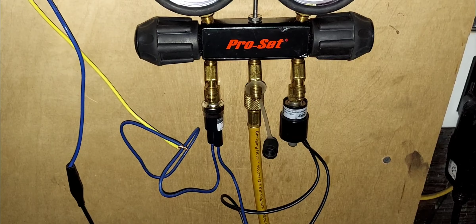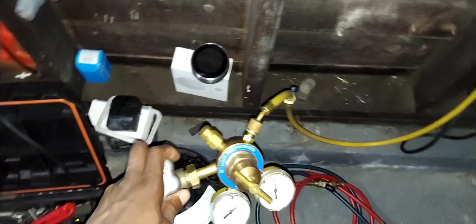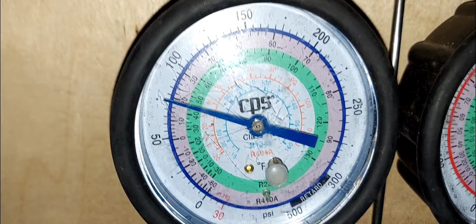So we're going to go ahead and trip this switch. We're going to trigger it. We know we've got to go up to 410 psi, so let's just close this gauge right here. So we're done with the low side. As a matter of fact, I've got to build the low side up and close it off so that we are staying online. Okay, so let's build that up. Okay, so we're good. R22, 75 psi back, we're good. So close that off for now. We're going to hold that pressure there. So the pressure is going to be trapped here. All right, so it's going to maintain.